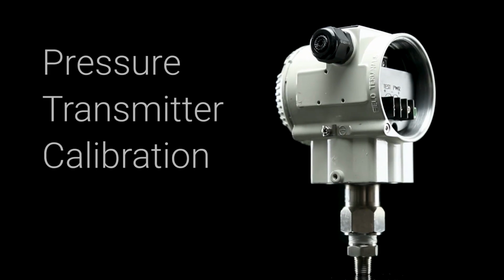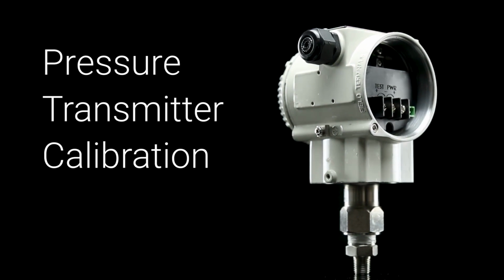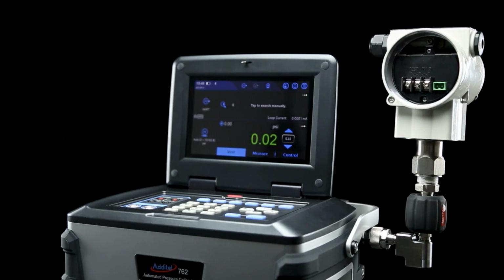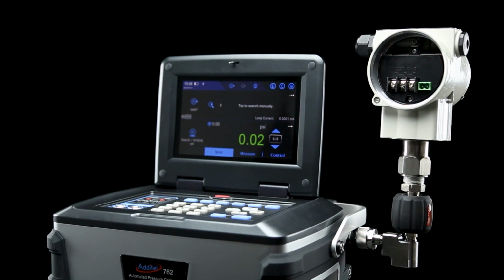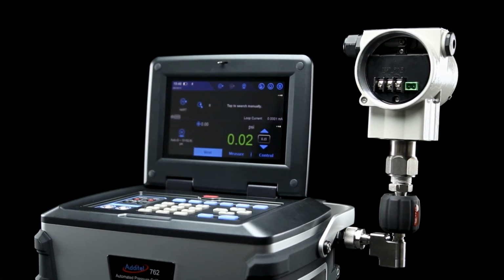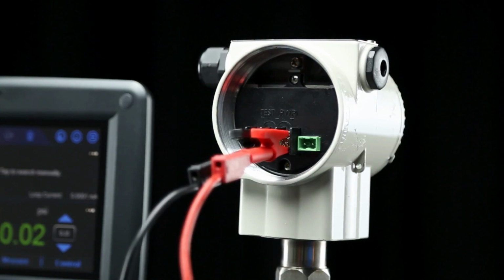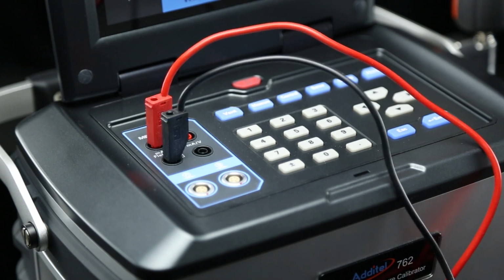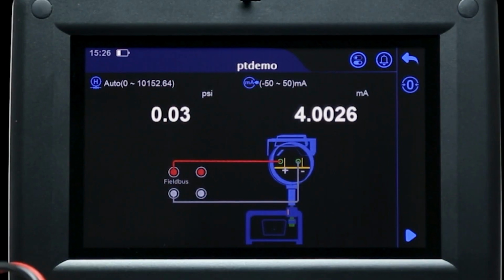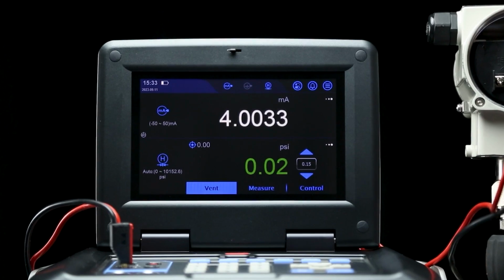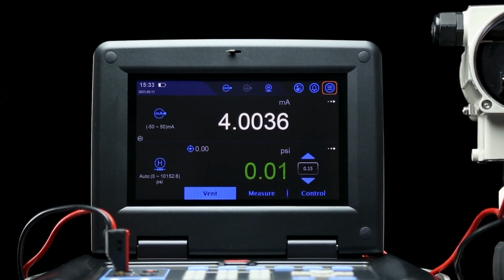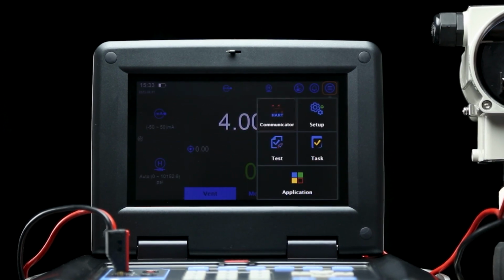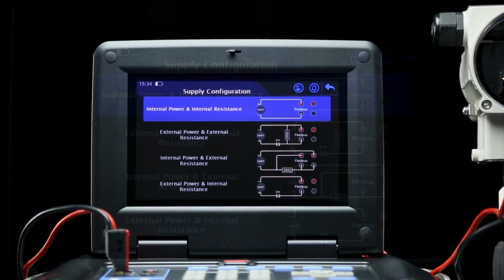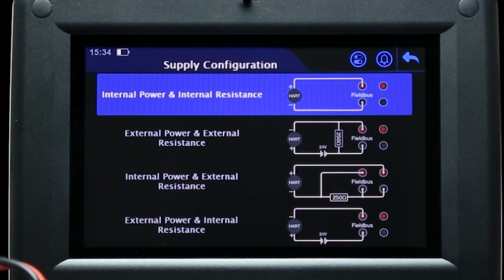Now that we've covered a simple calibration test, let's try something more automatic. To calibrate a 4 to 20 milliamp pressure transmitter, first attach the device to the quick connect fitting, then attach the electrical leads to the positive and negative terminals of the 762, which will provide loop power to the device. If you want to utilize HART communication, you can find the correct wiring setup by selecting the HART communicator button in the applications menu. For this transmitter, we'll use the internal power and internal resistance setup.